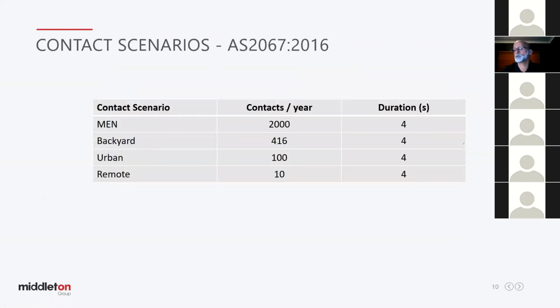These other scenarios, we talked quickly about the MEN, so in your houses, at taps, etc. In your backyard, so fences, taps in your backyard, you're going to be there less often, fewer times a year. So the standard allows for 416 contacts per year for a duration of 4 seconds. Urban, so you've got a conductive pole, say, out in your street, we're likely to be there less often than we are in our backyard or in our house.